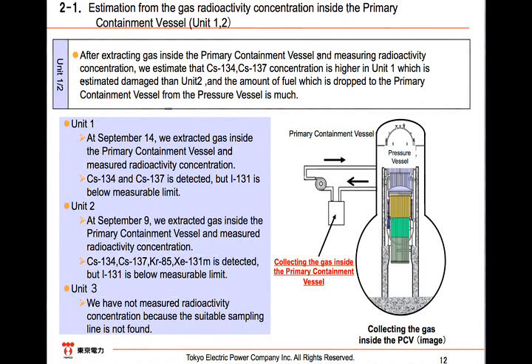In Unit 1, we detected cesium-134 and cesium-137 in the sampled gas on September 14th. In Unit 2, in addition to cesium-134 and 137, krypton-85 and xenon-131M were also found in the gas sample taken on September 9th. We estimated that more fuel fell off from the RPV to the PCV in Unit 1 than in Unit 2, as it turned out that cesium concentration was higher in Unit 1.